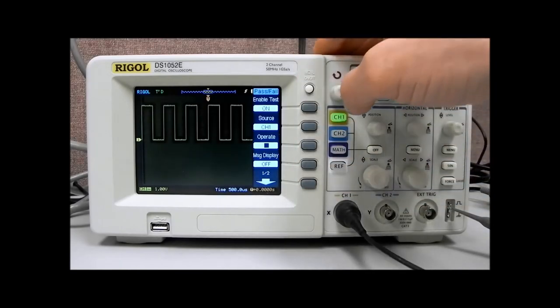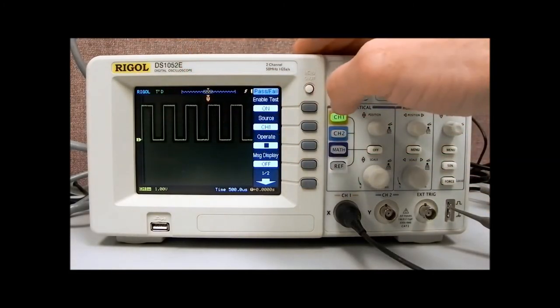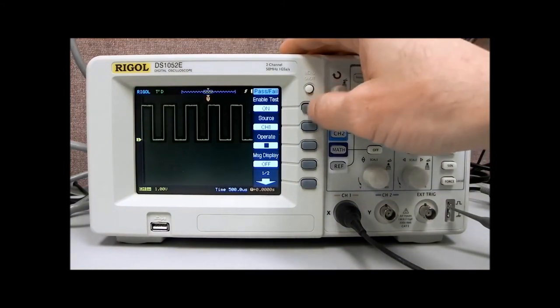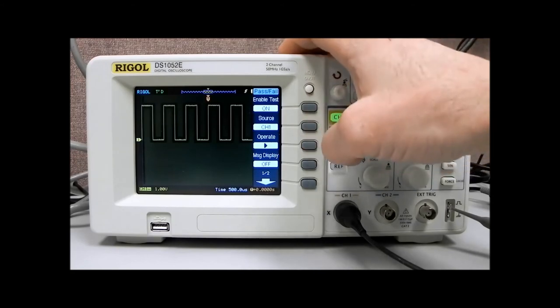So we can enable that test. Now you can see, by enabling the mask, we have basically put a framework around the incoming signal that says, okay, this is what's going to be a pass area, and then we can operate that.